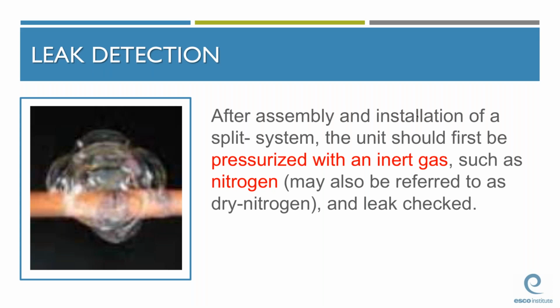And if you want to do a quick test, once you get a nitrogen tank, and I'm talking about a small tank, not the big A tanks, flip the tank upside down and crack open the valve, and you'll see all the water shooting out. So the nitrogen that we typically use in our classes is definitely not dry and contains a decent amount of water.